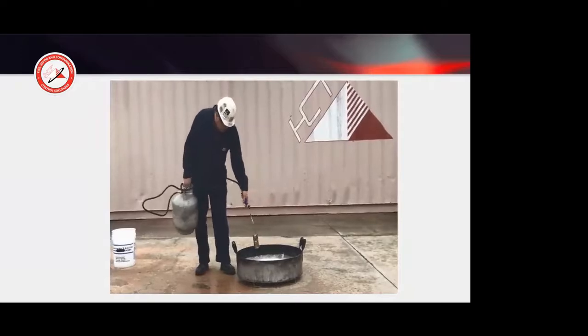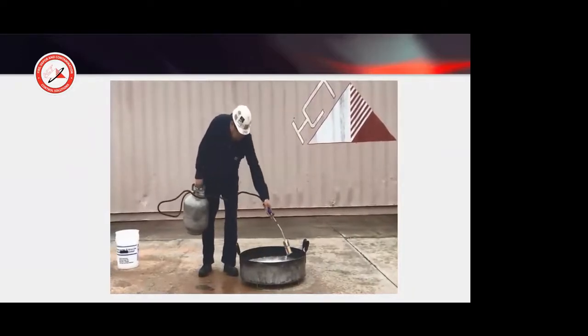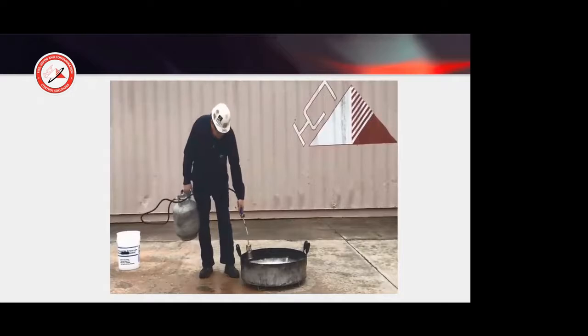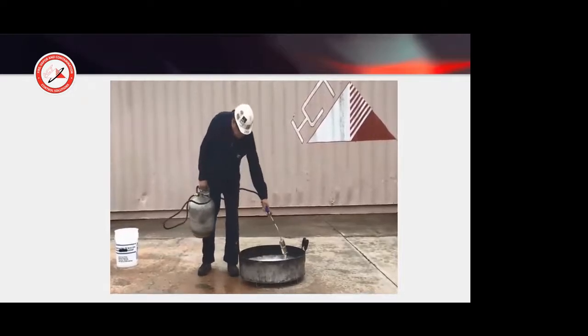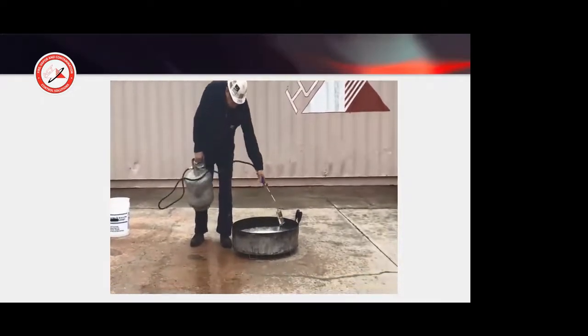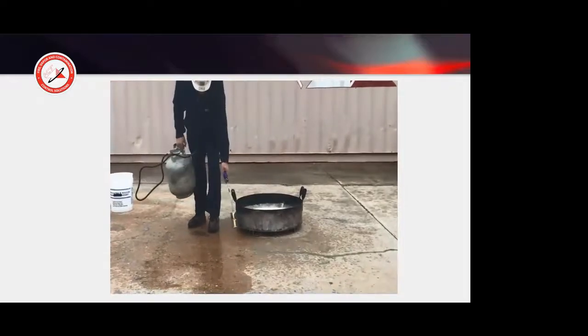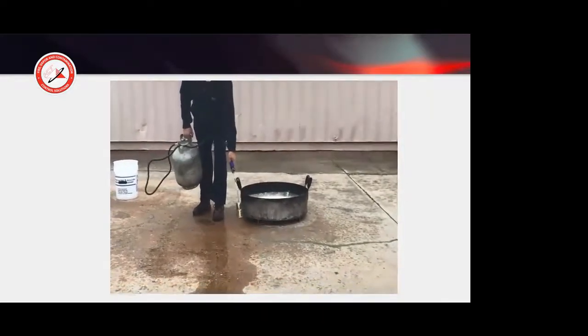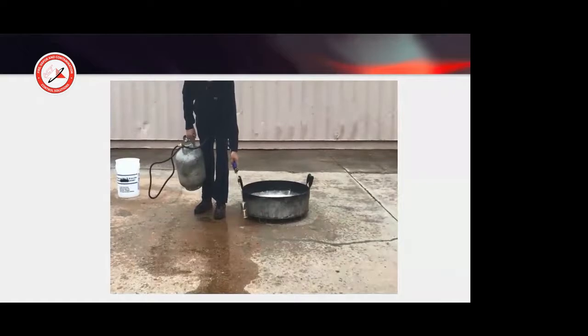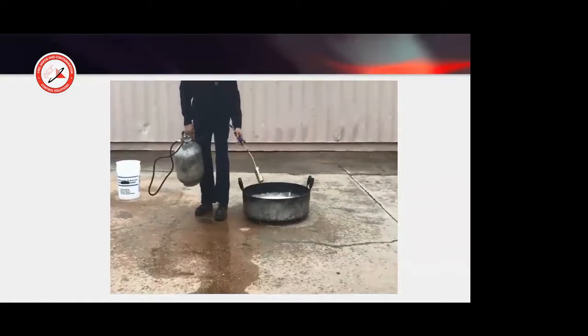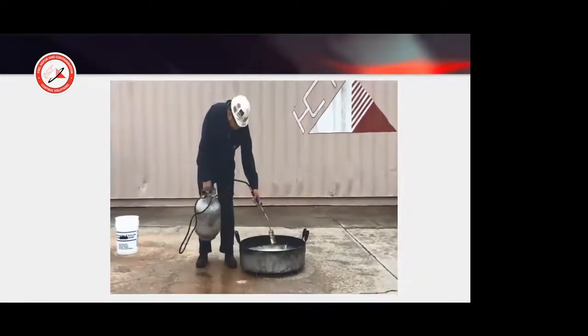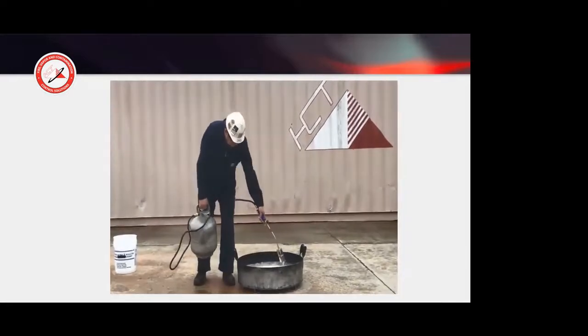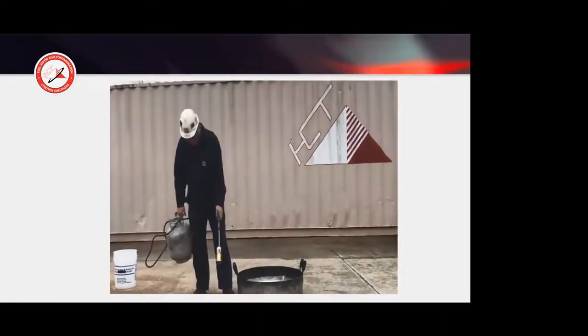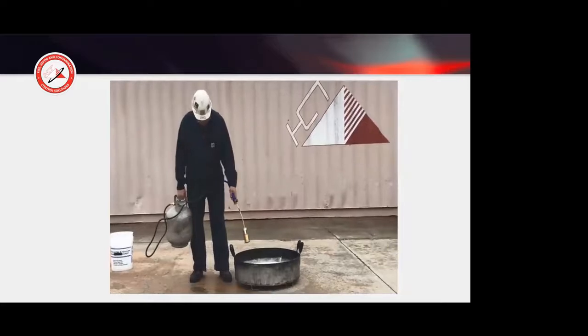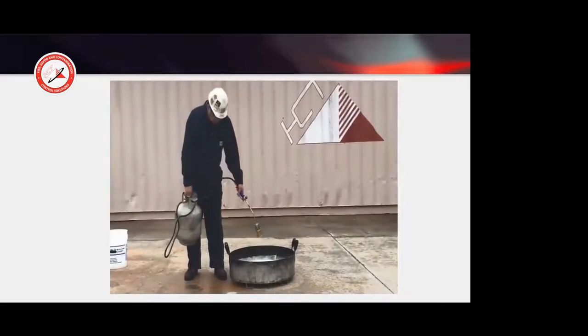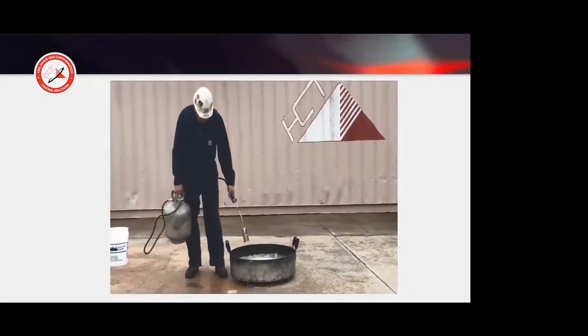If we were to put down a foam blanket here on this test, you would see lots of foam bubbles. When you lit the torch here, you would see candling of the vapors that are in the bubbles, but you would not get a free burn. We've done this with our Class B foams and some competitive Class B foams. And what happens is some vapors get trapped in the bubbles. So as soon as you hit it, you get some candling of the bubbles. But again, that's not qualification as not passing. So the foam will pass the 1 minute test.